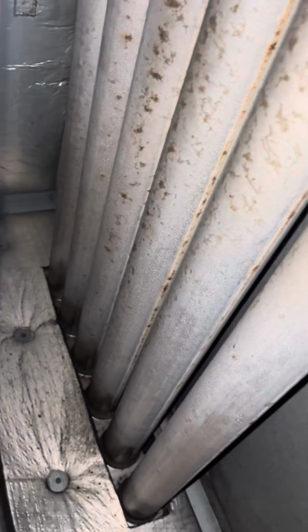So like I said, when you see rust on these, you can go ahead and recommend they replace it before we get to that point, because that's when it becomes hazardous to whoever's occupying that space down there. These blowers sit on top of this and blow down, cooling the heat - that blower's job is to blow it down in there. They got cracks in this, somebody ain't gonna like it, you're gonna be spending way more money. Now I ain't gonna say all that.